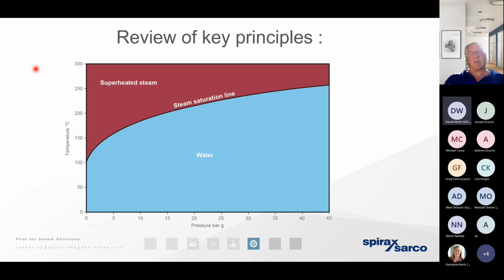We've also got the pressure temperature relationship, and this is critically important to understand. So we've mentioned that at 0 bar gauge, water boils at 100 degrees, and therefore the temperature of the steam at 0 bar gauge is also 100 degrees. In reality, our client is going to be producing steam under pressure, and at pressure of 10 bar gauge, well, that water is going to boil at 184 degrees. Therefore, the temperature of the steam is 184 degrees. If we've reduced the pressure, in order to manipulate the pressure at the process, let's say the pressure has fallen to 2 bar gauge to control the temperature at 130. Well, it tells us that we can do that by observing that pressure temperature relationship using a very, very simple and basic pressure reducing valve in order to do that.